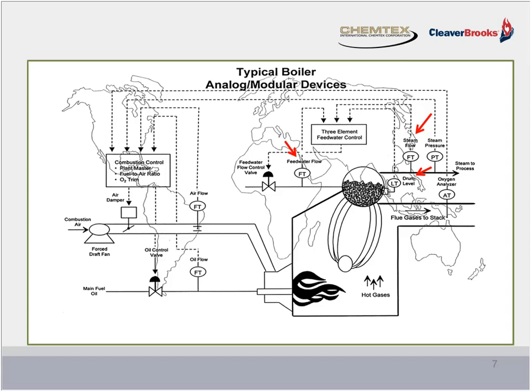And then you also have a feed-forward steam flow transmitter, which senses the demand increase or decrease, and then sends the signal to the third element, which is the feed water regulating valve. Now, this control scheme largely mitigates the rapid swings in level, which causes carryover and nuisance shutdowns due to a low water condition.